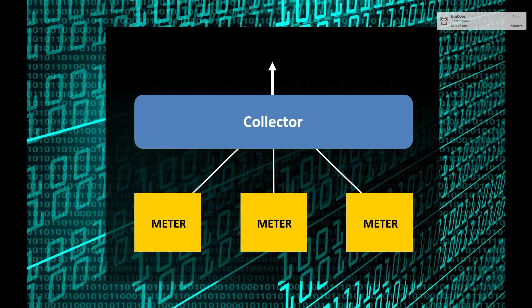PowerHawk meters, on the other hand, can support Modbus RS-485 interface communication simultaneous with Ethernet IP connection. Further, on the IP side, the PowerHawk meter can be a slave to multiple building automation system masters using Modbus TCP/IP or BACnet IP protocols. As an aside, this is still the traditional collector architecture.